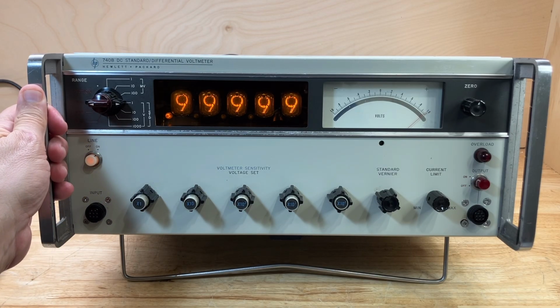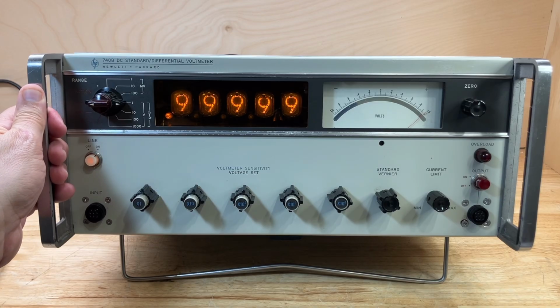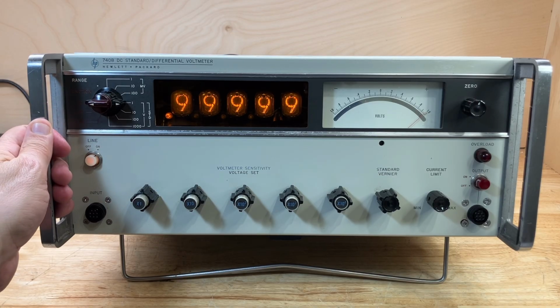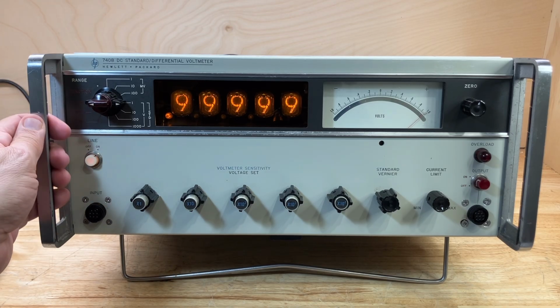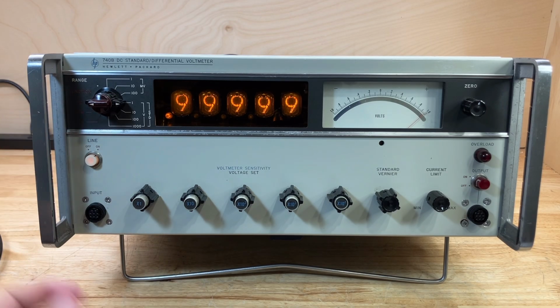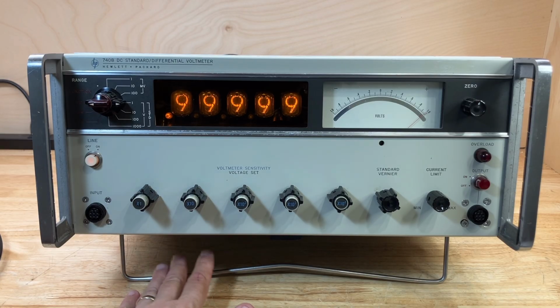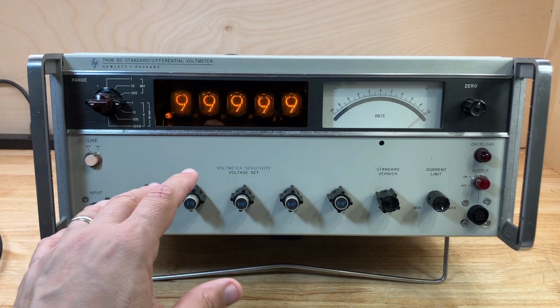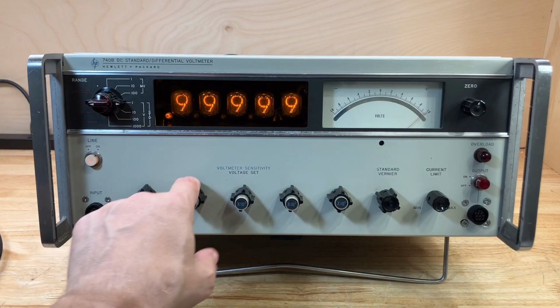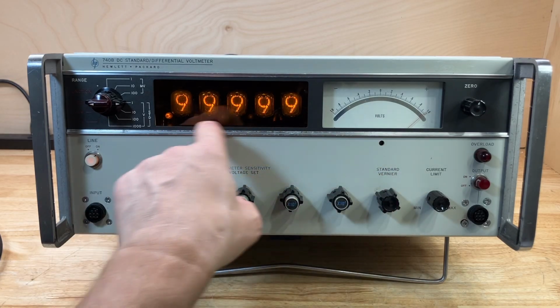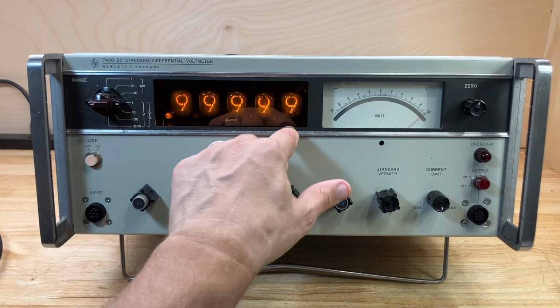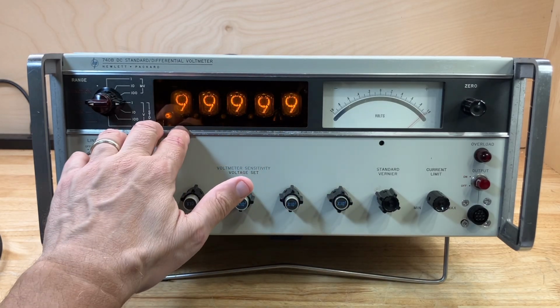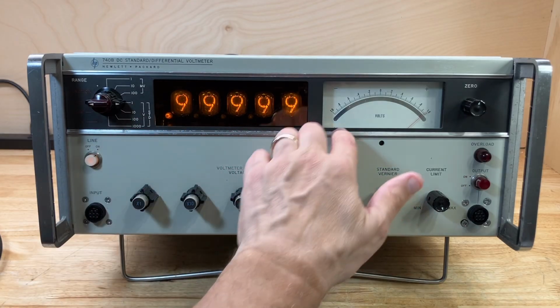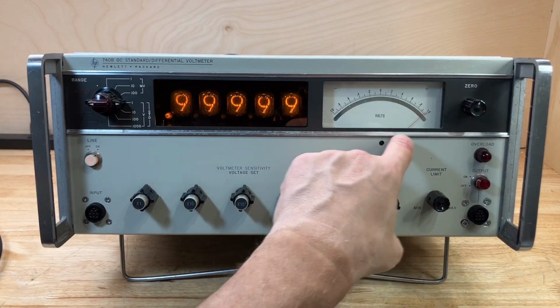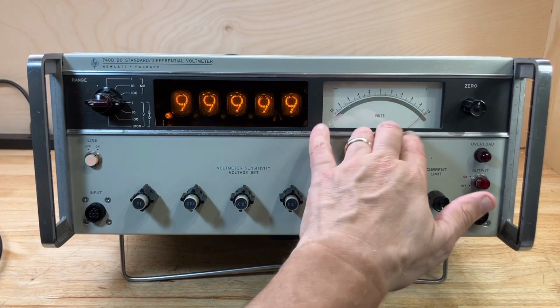The HP740B DC standard differential voltmeter is actually 4 different instruments in one enclosure. It really can be configured to be 4 different instruments inside one enclosure. It reuses most of the same circuitry for each of those 4 instruments. Primarily, it's used as a DC voltage standard. It has 5.5 digits or 6 digits of resolution. The first 5 digits are indicated on the Nixie tube neon displays, and the least significant digit is indicated by reading off the meter for the 6th digit.